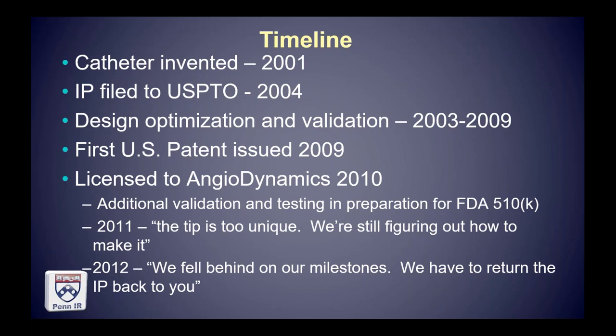Because the tip was so different — when you make a hemodialysis catheter it's basically a double-D extruded polyurethane tube that is cut, with holes skived on the side by tool stamping or laser skiving — they found that the tip of the vector flow catheter was too unique. After a year from the licensure agreement they were still trying to figure out how to make it, and then came back saying they'd reached an impasse, fallen behind on milestones, and would have to return the IP back to me.